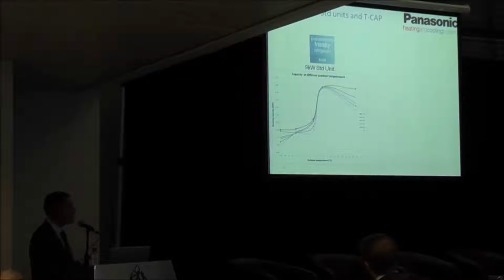So the unit is tested at air at 7 and water at 35. So this is a standard 9 kilowatt unit. But see what happens once the ambient drops below 9 degrees C. It doesn't just decrease, it plummets. And that's one of the issues that we've had in the past with air-to-water heat pumps, is that they weren't correctly designed for the application. It's fine at air at 7, you're getting a duty, but when the air drops to 0 or minus 5 or minus 10, we have considerable issues. So you have to size it for the proper ambient temperature.